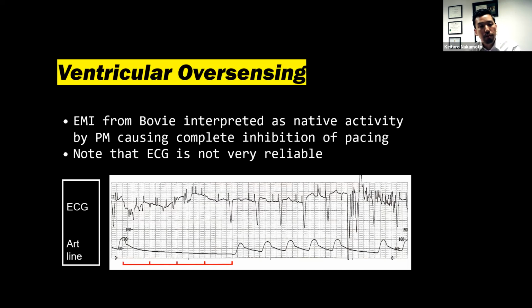This is an example of ventricular oversensing, like we talked about. This is when the EMI from the Bovie is interpreted as native activity by the pacemaker. You can see on the ECG all these spikes, which is probably the Bovie. This is sensed by the pacemaker, which thinks it's native activity, and it completely inhibits the pacing function of the pacemaker. And as you can see on the art line, this patient has no pulse for quite a long time. Note that the ECG is not very reliable.